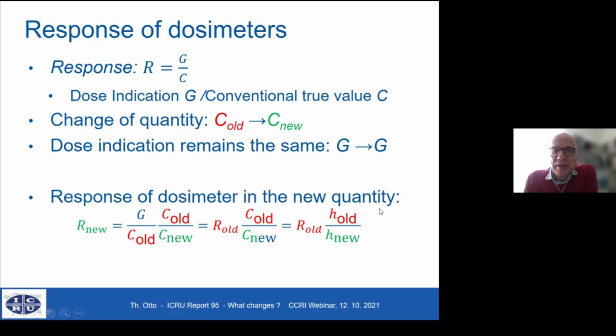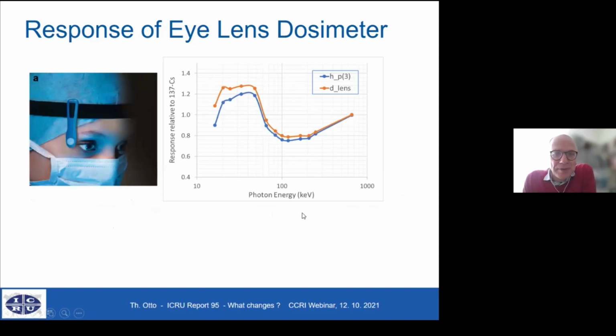And this I have been doing after the publication of the report with a number of dosimeter types, to evaluate what happens with present dosimeters which are used in practice and how they can be used for the new quantities. I spare myself to show a skin dosimeter or extremity dosimeter because I hope you have seen that the two calibration curves are so similar that there is no doubt that the HP 0.07 dosimeter of nowadays will work for D local skin. Here's a lens dosimeter, which is commercially available.